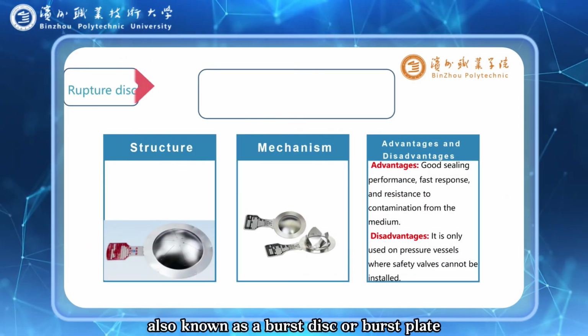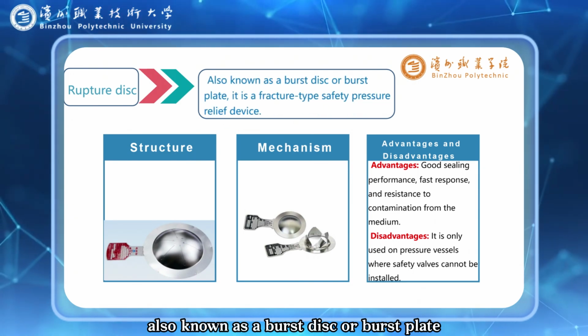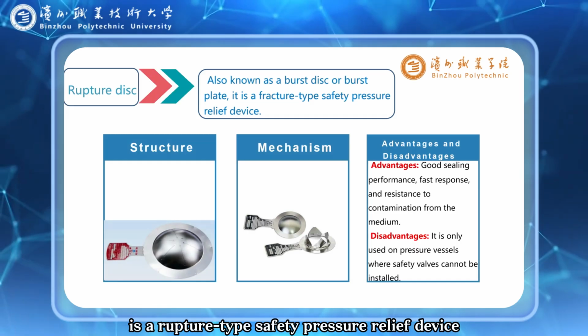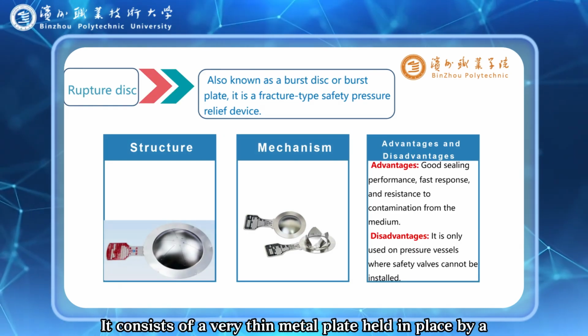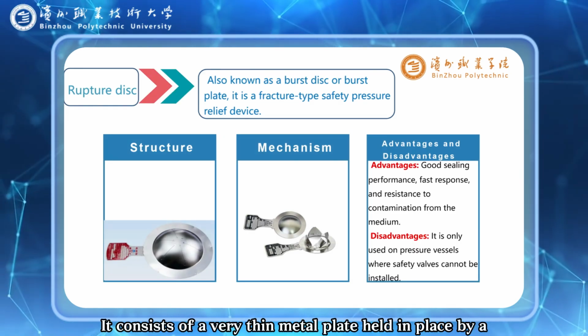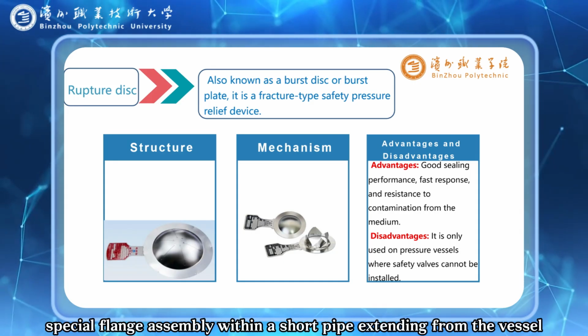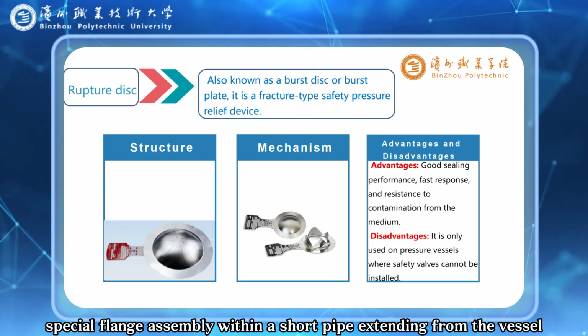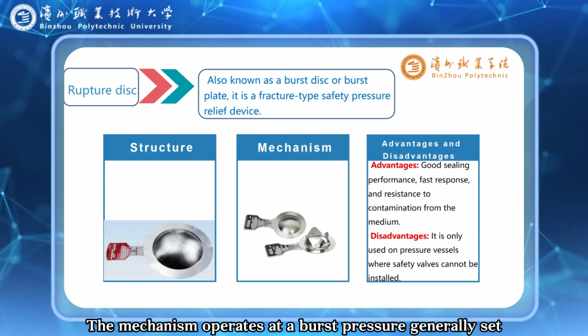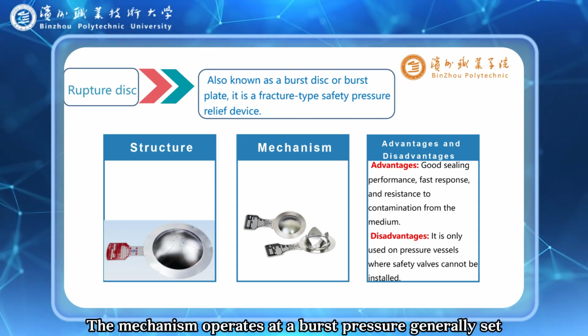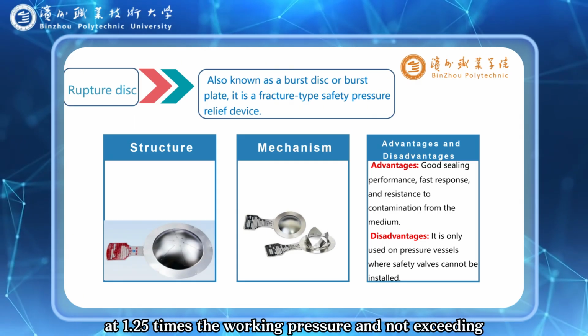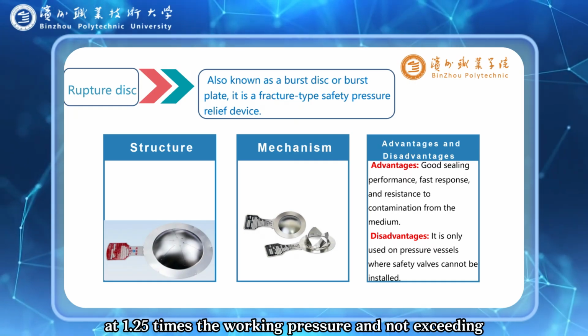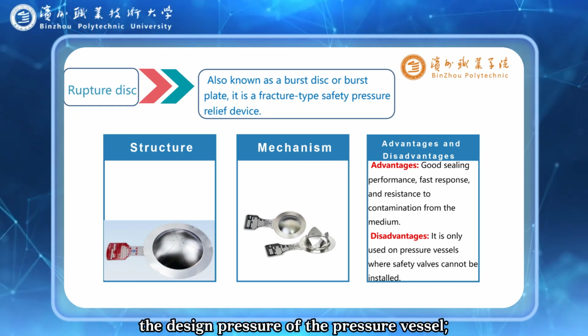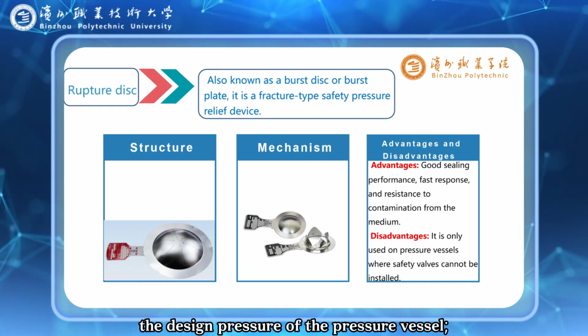A rupture disc, also known as a burst disc or burst plate, is a rupture-type safety pressure relief device. It consists of a very thin metal plate, held in place by a special flange assembly within a short pipe extending from the vessel. The mechanism operates at a burst pressure, generally set at 1.25 times the working pressure and not exceeding the design pressure of the pressure vessel.